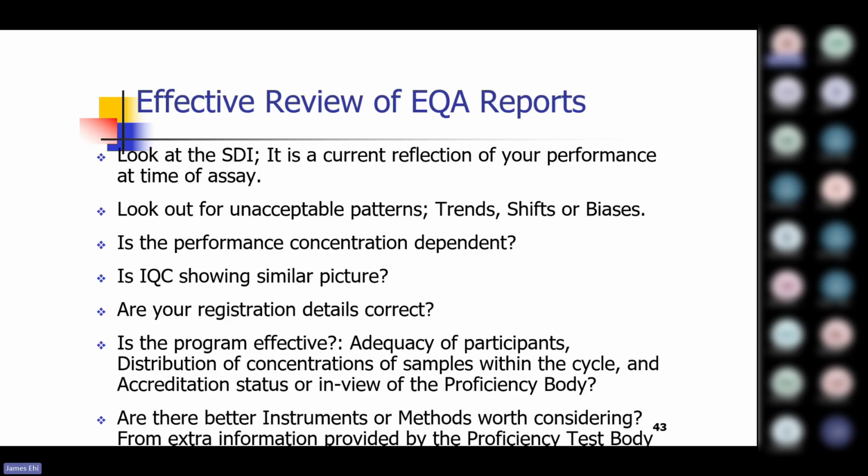Then, are you registered with the correct details? Some people have registered wrong details and they are always carrying out corrective troubleshooting actions. Check your methodology. Go to the package insert. Many people don't like reading. They don't pick the package insert method from the manufacturer. They don't compare. When they are registering for their EQA program, they never ask for help. Which methodology is this? They feel they know everything. Take time out and ask for help where you are not sure. Don't just pick the one closest in answer to it.